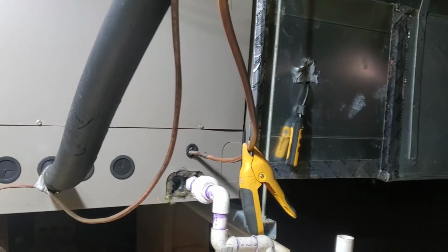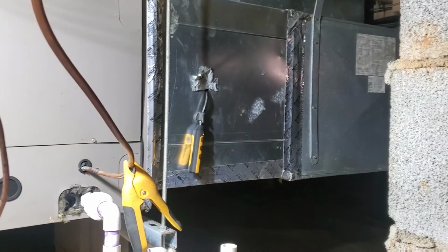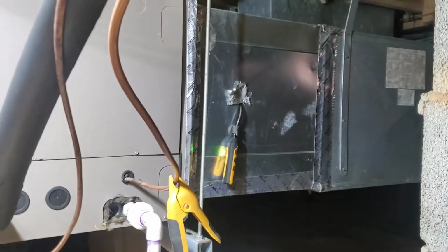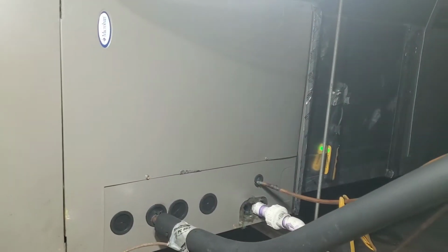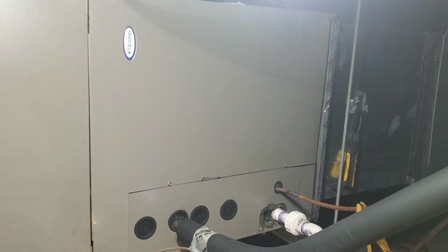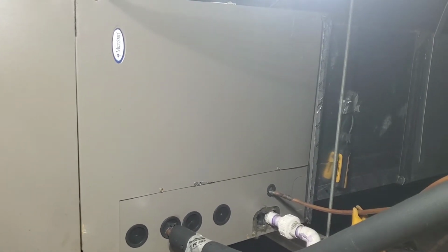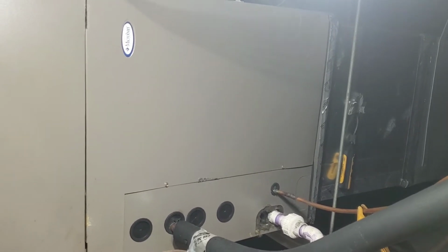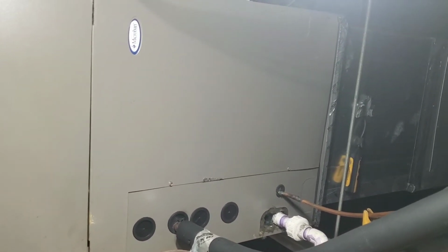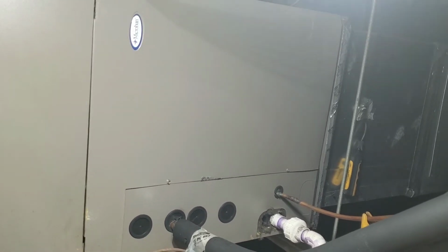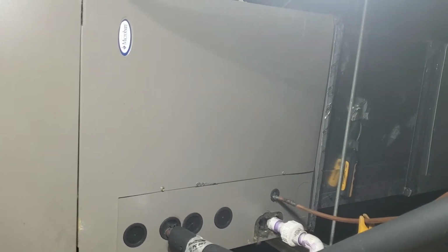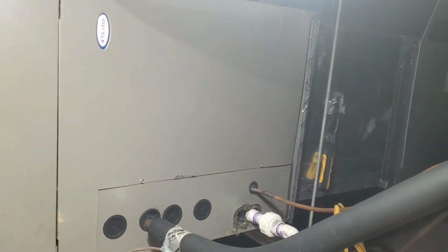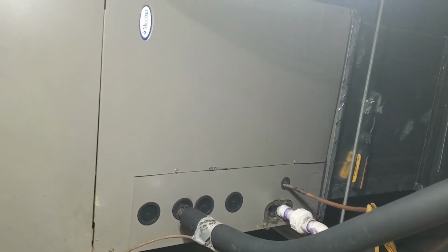Your liquid line should always be a few degrees warmer than your return air, because that means you've got a little bit of heat left over as that refrigerant leaves the indoor coil. If your heat pump is undercharged, then that means that your approach temperature is going to be closer to zero, and that's because you're just not making a warm enough indoor coil, and that heat that's generated in that indoor coil is being just used up as quick as it can get in there. So your liquid line temperature ends up being the same temperature as your return temperature, because we just don't have enough heat in that indoor coil.